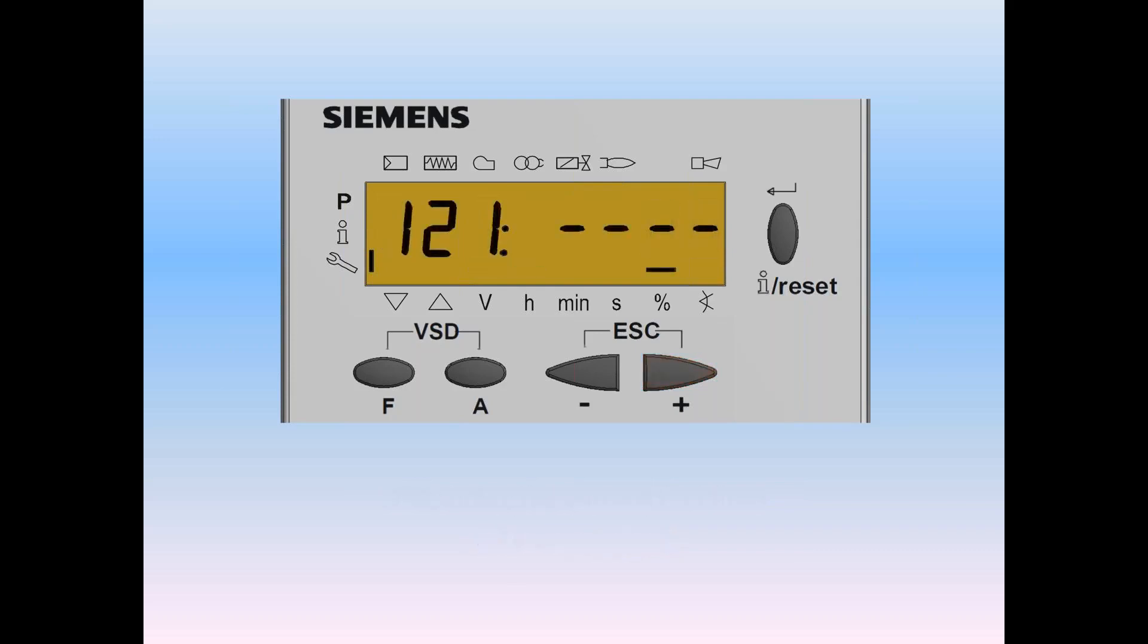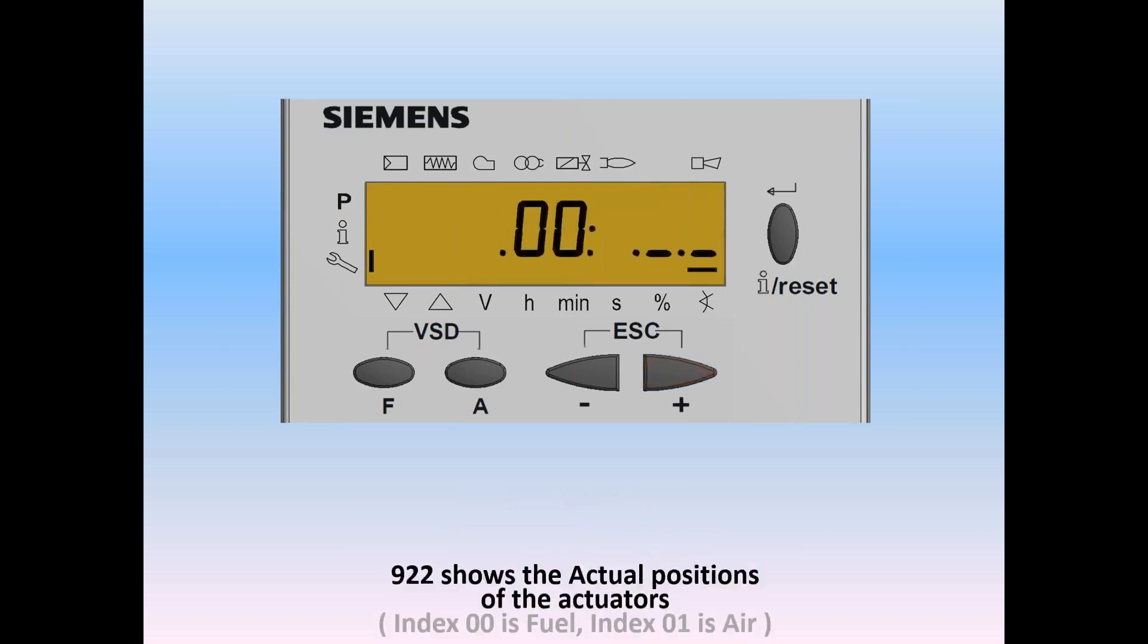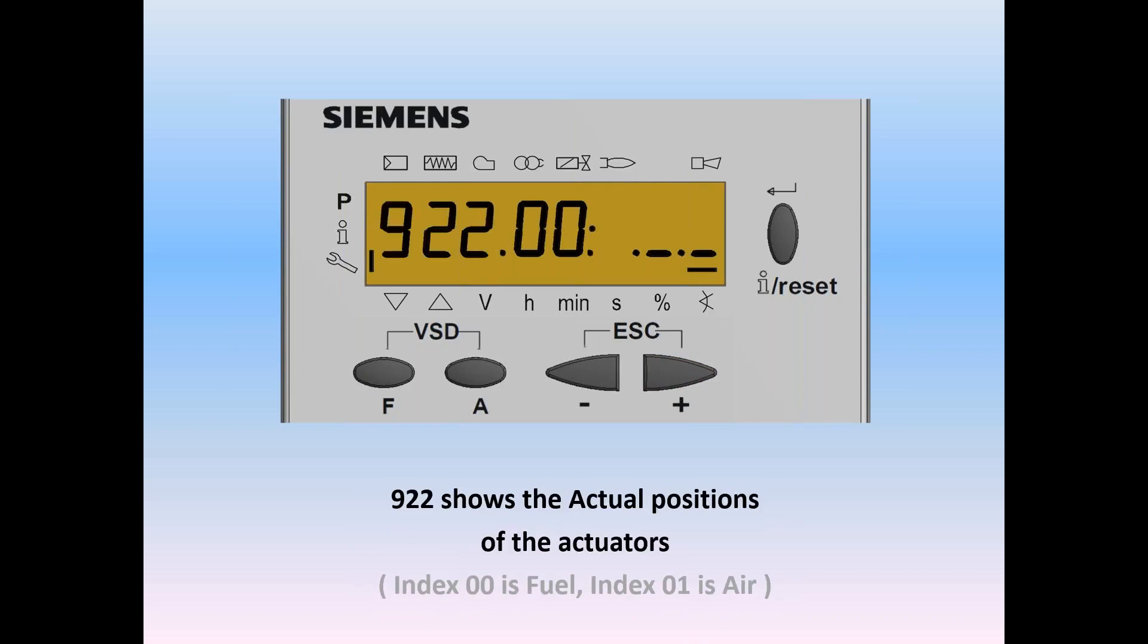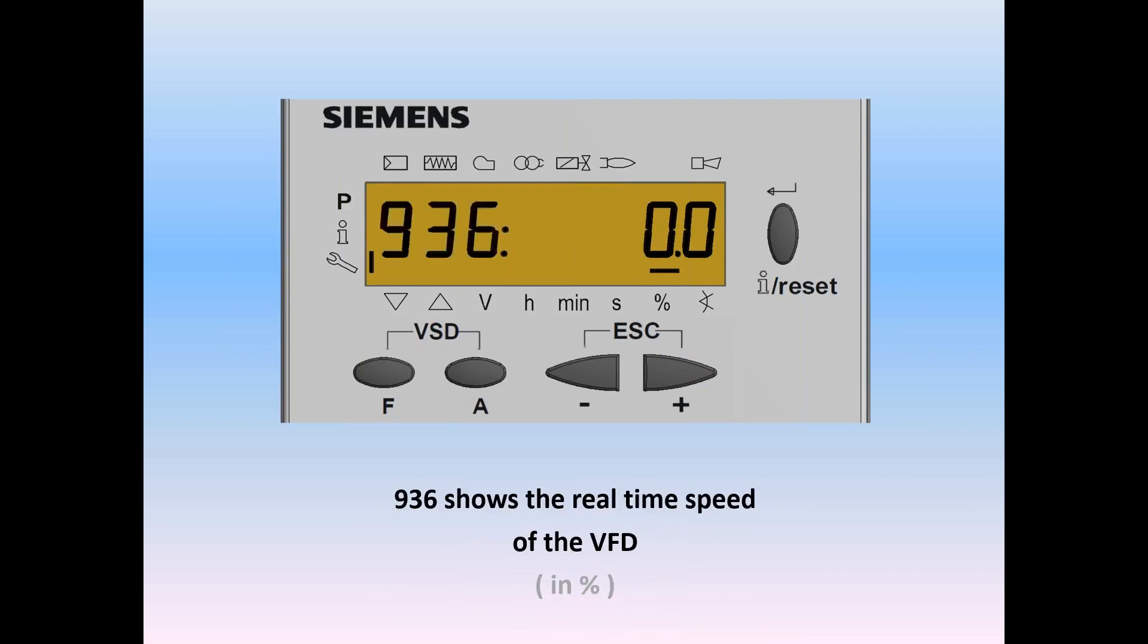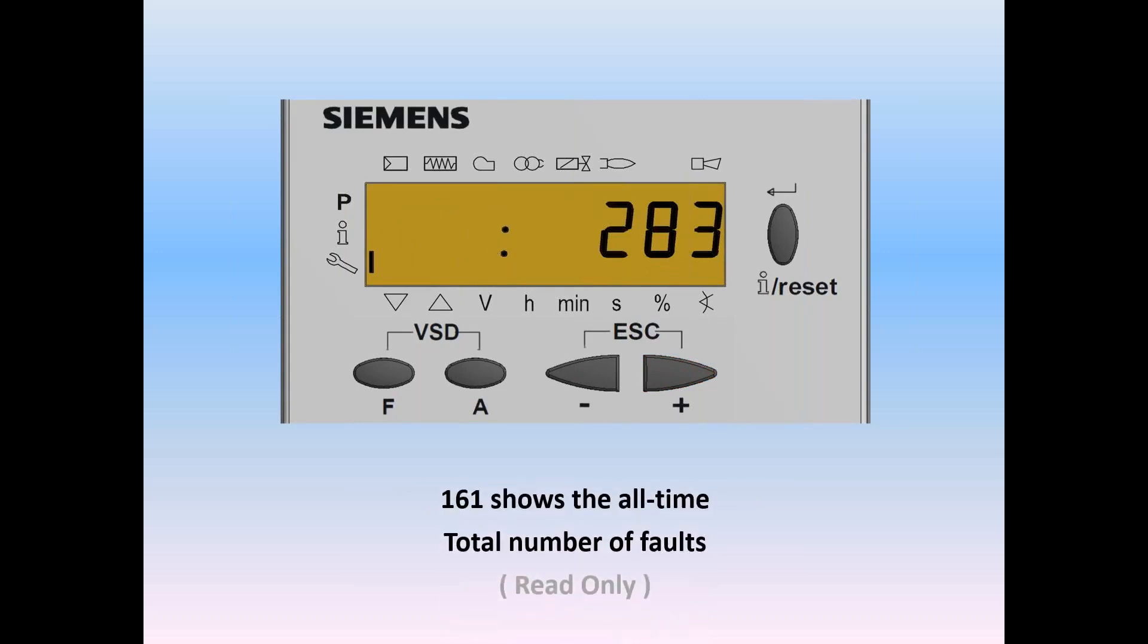Do a plus. And we'll move on to the next screen. That would be 121. 121 shows the manual firing rate. In this case, we don't have a manual firing rate. Do the plus key. And we move on to 922. 922 shows the actual positions of the actuator. This particular parameter has indexes. Zero, zero is fuel. Zero, one is air. We'll look at that later. Do a plus. And we get 936. 936 shows us the real-time speed of a VFD if we're so equipped. In this case, it's zero. Do a plus. 161 shows us the total number of faults. It's read-only. You can't change it. It tells you that this system has experienced 283 faults in its entire lifetime.